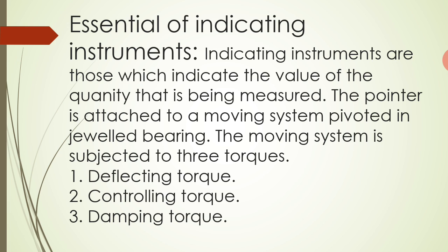Next is controlling torque. The deflection of the moving system would be indefinite if there were no controlling or restoring torque. This torque opposes the deflecting torque and increases with the deflection of the moving system. The pointer is brought to rest at a position where the two torques are equal.